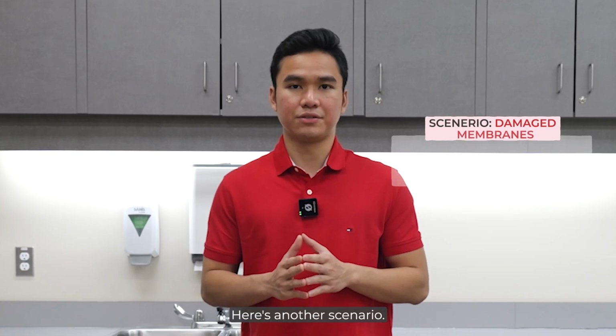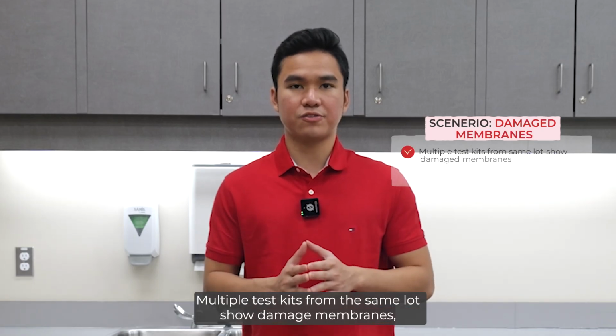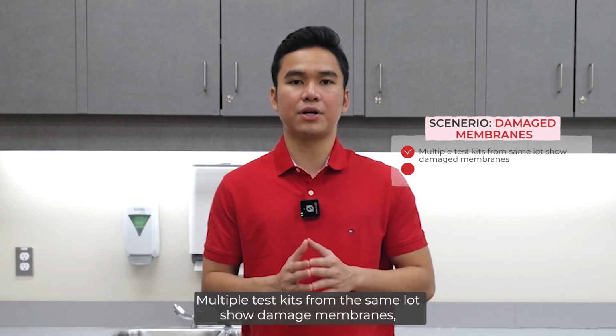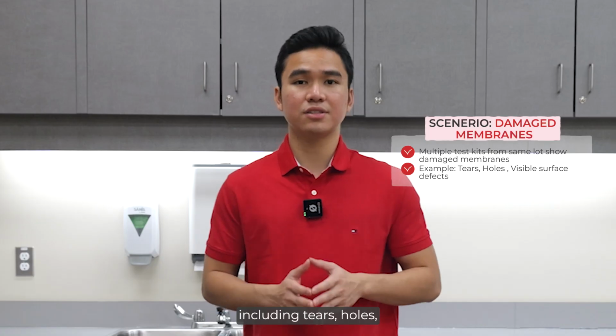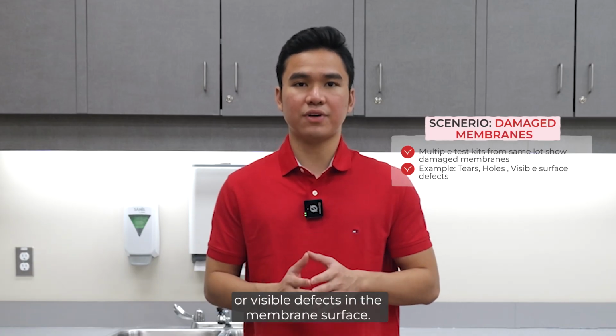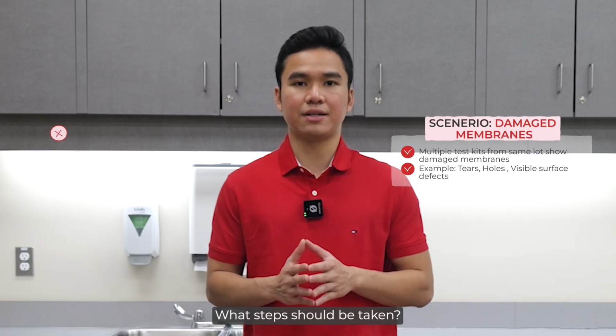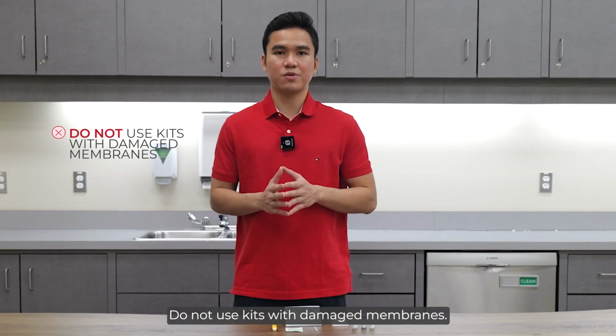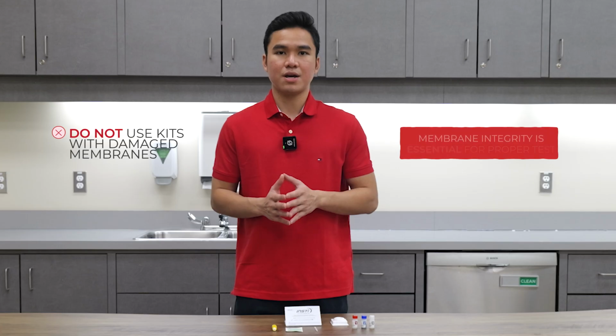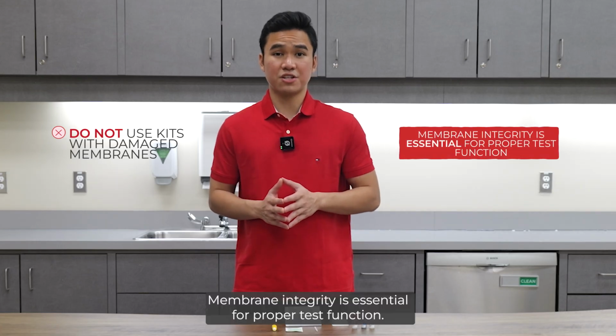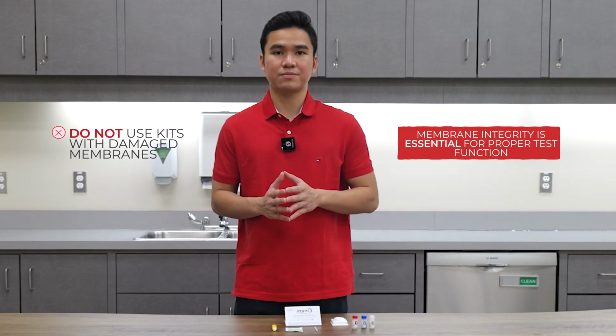Here's another scenario. Multiple test kits from the same lot show damaged membranes, including tears, holes, or visible defects in the membrane surface. What steps should be taken? Do not use kits with damaged membranes. Membrane integrity is essential for proper test function.